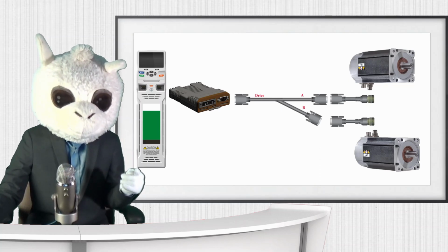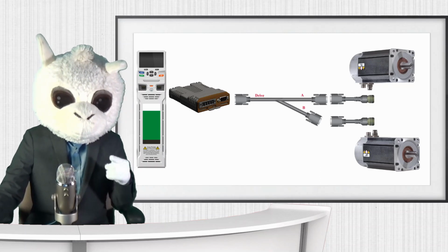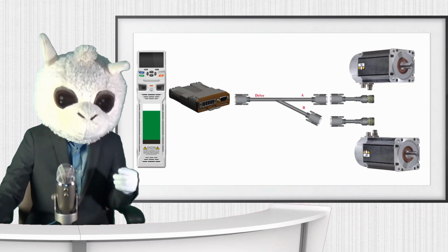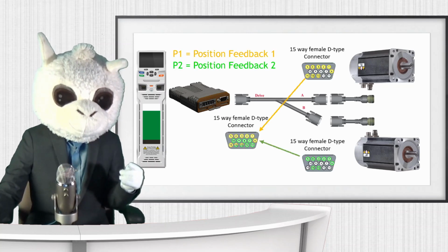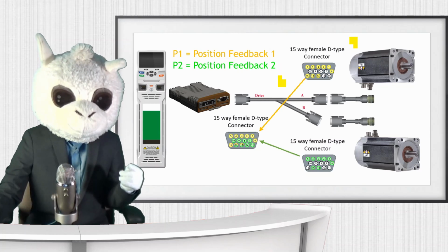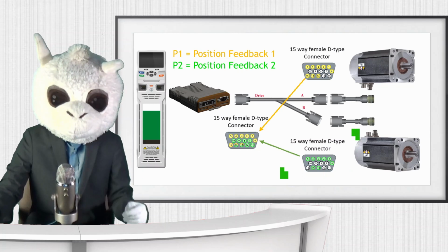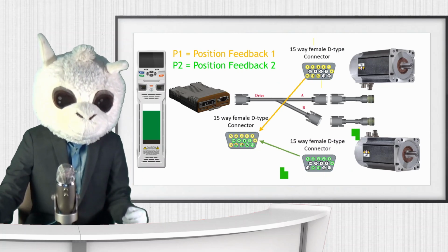Now, a lot of individuals think that it's just a splitter cable, and it's not. If it was a splitter cable, you couldn't hook up 2 motors just like this, exactly the same, and plug it in. So this is what they've done. You can see over here that the yellow dots are how the first motor is wired up, and the second motor is wired up using the green dots. Well, you can see they're exactly the same except for the thermistor.